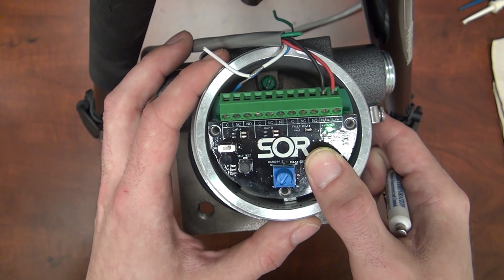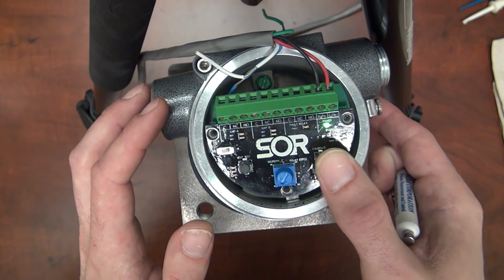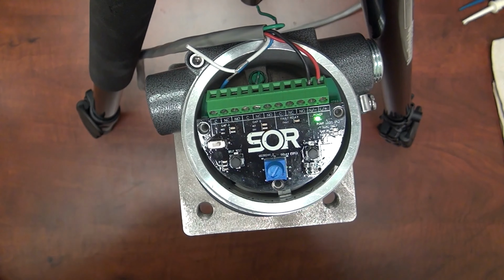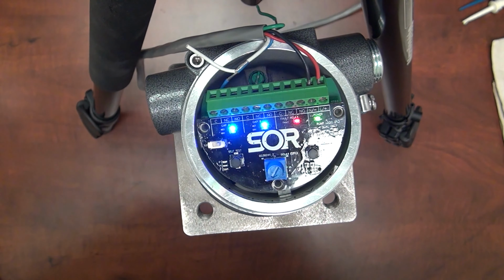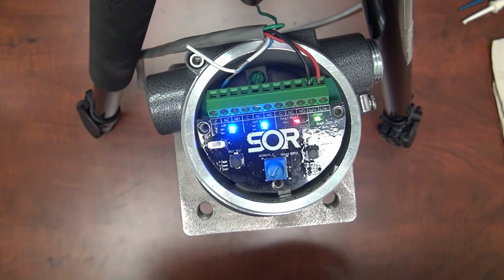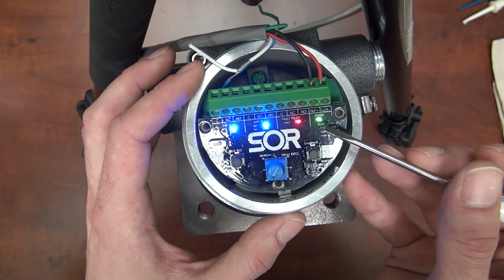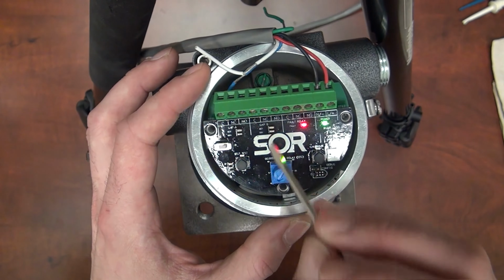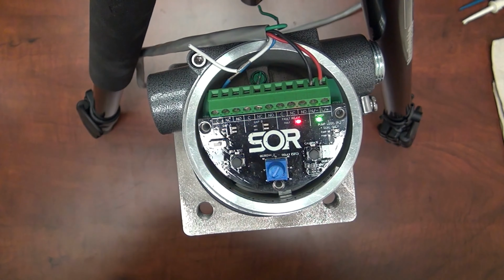Press and hold the button for approximately 3 seconds. When the lights begin flashing again, it can be released, and now the calibration will proceed without further input from the user. Our dry calibration is now complete. We can see though that we still have a fault indicated here, and we can see that it is now our wet LEDs that are flashing. This is an indication that a wet calibration is now required.